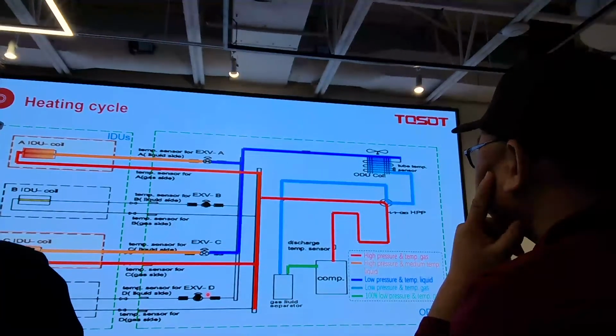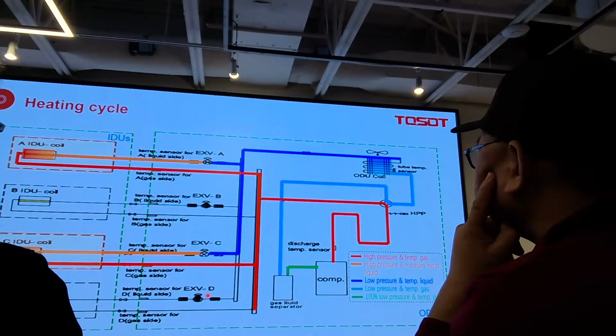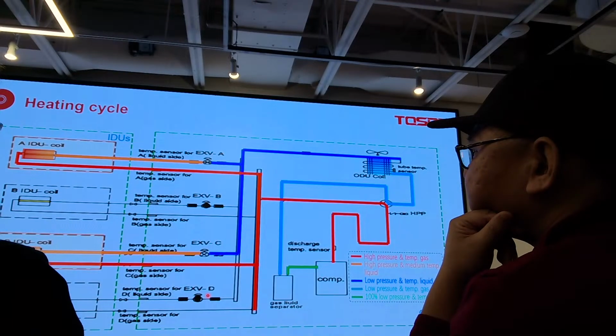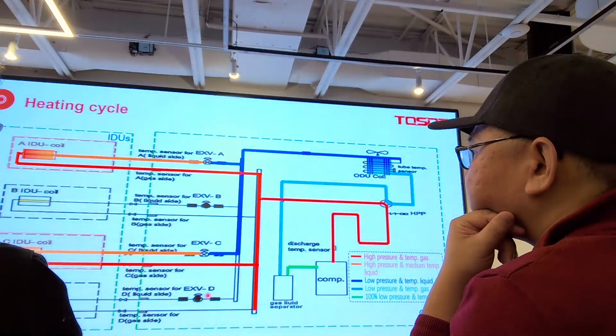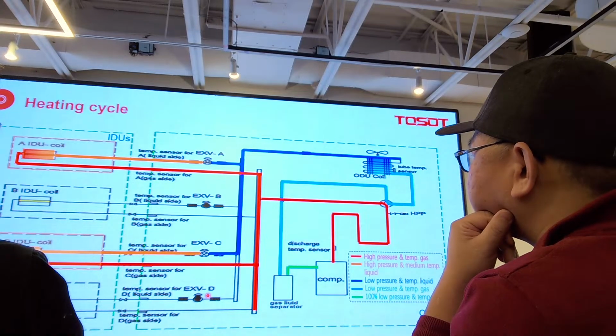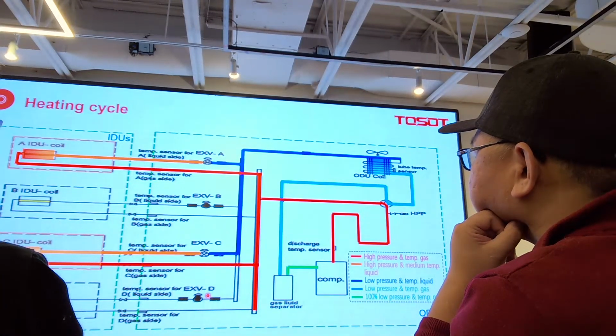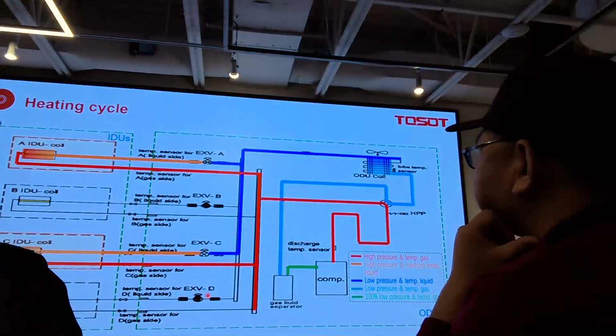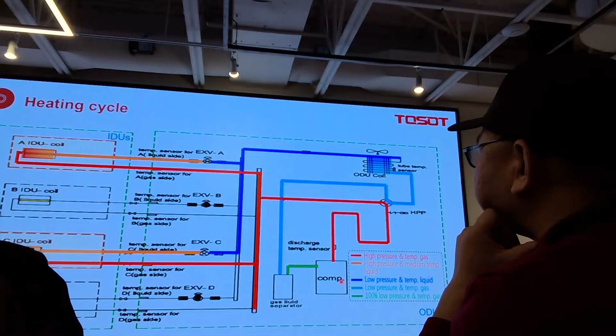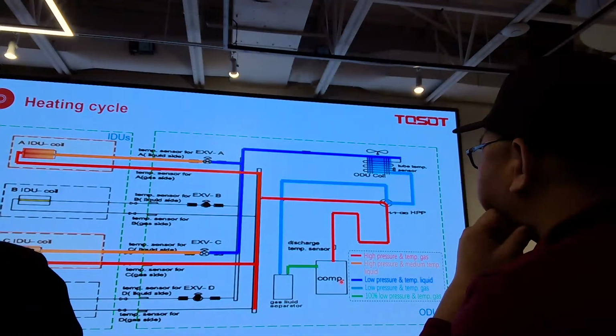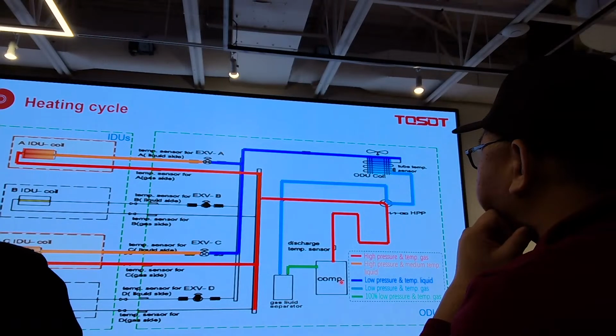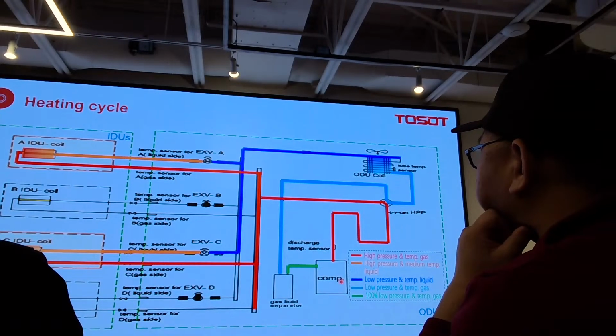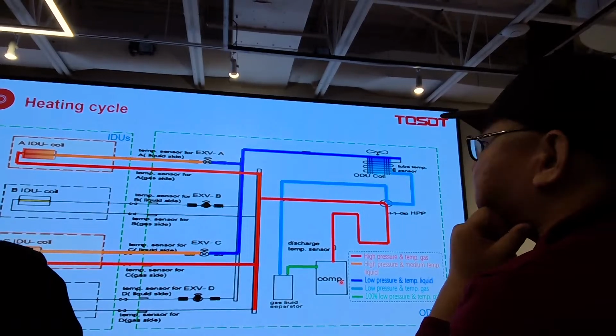Okay, I'll give you the answer. Actually, this control algorithm is almost the same no matter the manufacturer, which means even Daikin, Mitsubishi, and also LG is the same, for the multi-zone system. And I'm afraid that for this, in unit B and D, the metering device is just opened a little bit, and I will show you the reason why.